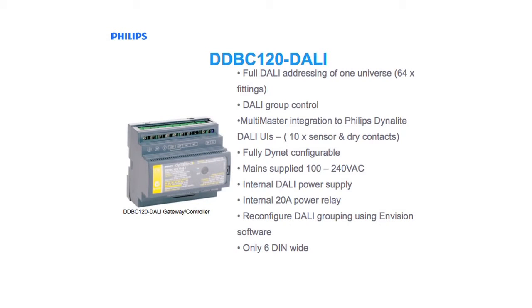The DDBC 120 DALI gateway controller is capable of driving a full DALI universe of 64 fittings. The unit is mains powered and requires no external devices for DALI communication. This unit supports user interfaces connected directly to the DALI network, allowing for sensors and dry contact inputs to use the same communication as DALI light fittings. A max of 10 user interfaces can be connected to the load controller.